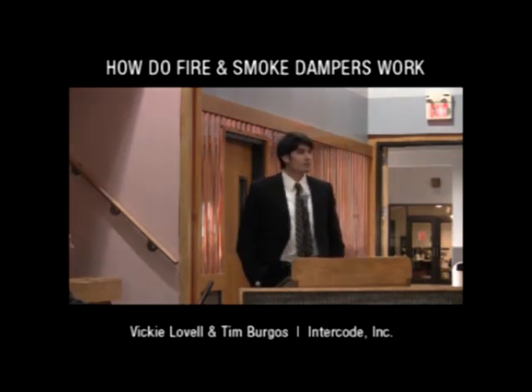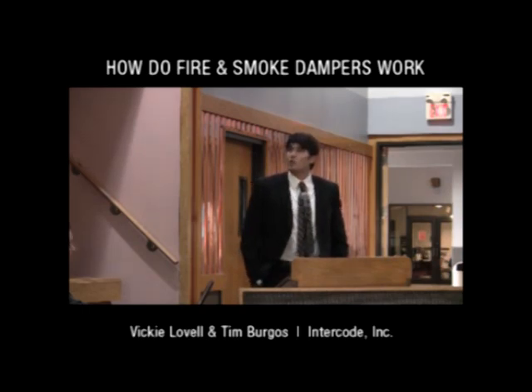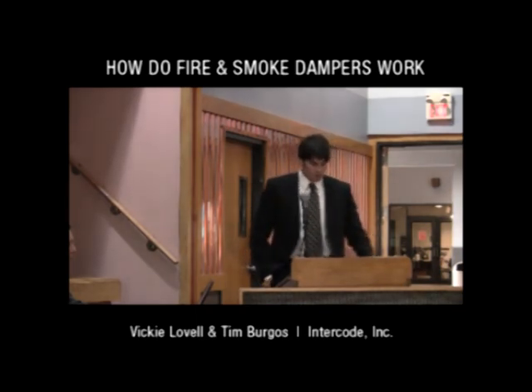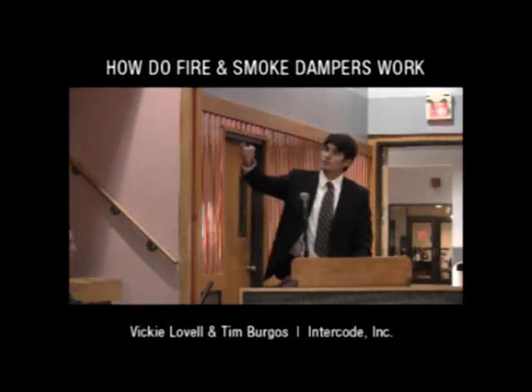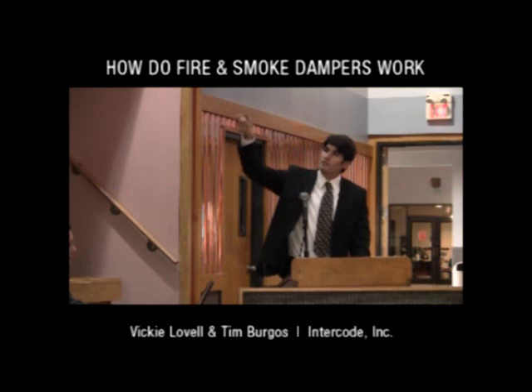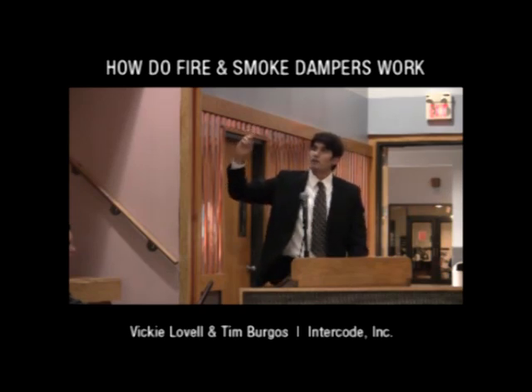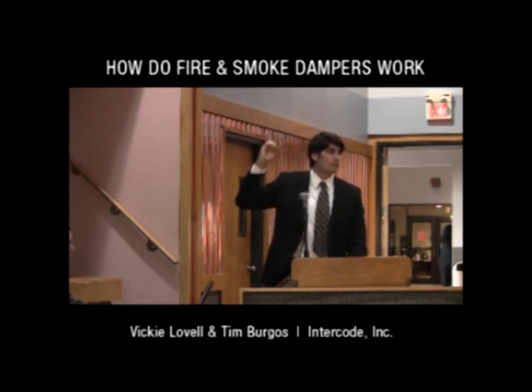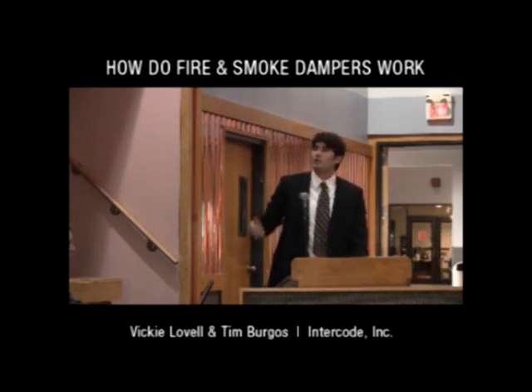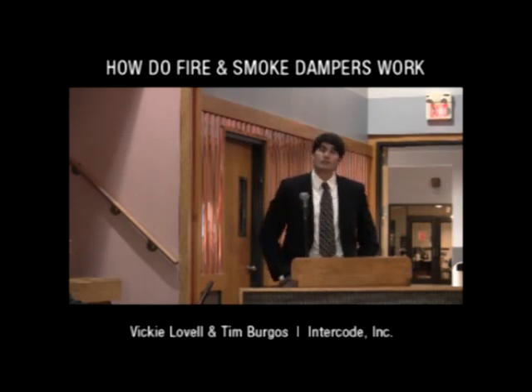There's two different types of dampers besides smoke and fire. I'm talking about the operation of a damper. One type, as you see, is a fusible link operated damper. What a fusible link is, you see on the picture, there's a link that holds up the damper itself, which in this case, for the fire damper, is a curtain damper. And at a specific temperature, that link will melt, causing the damper to close. And most fire dampers, ceiling dampers, and some combination fire smoke dampers are operated using this system.